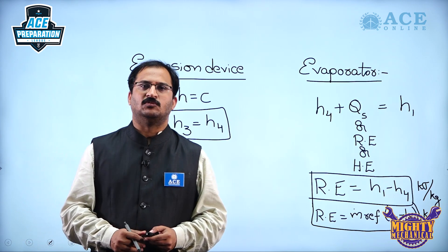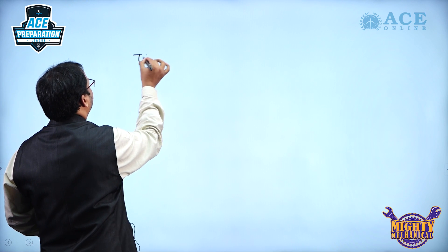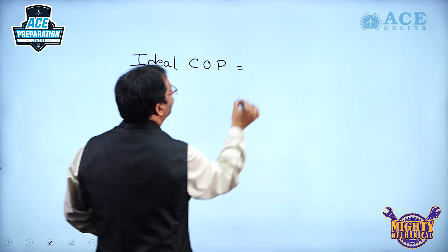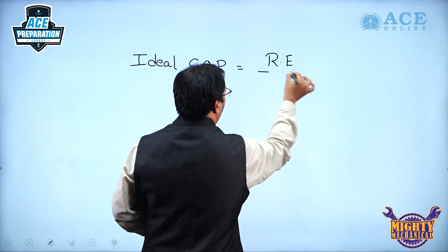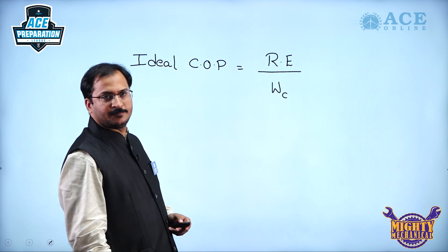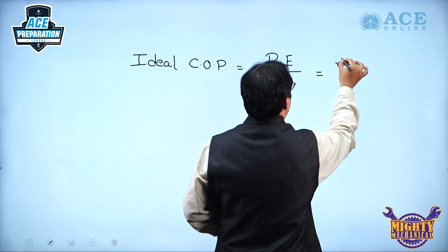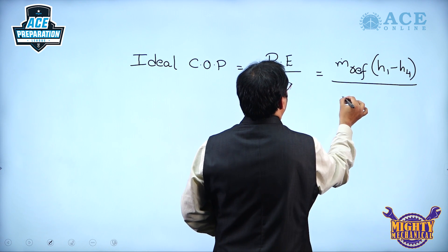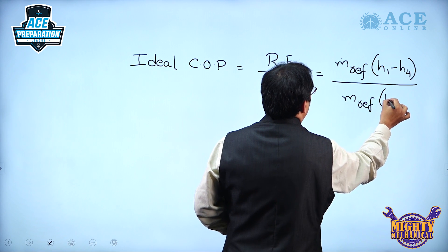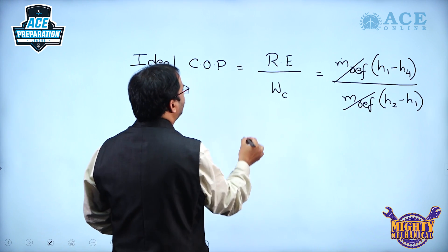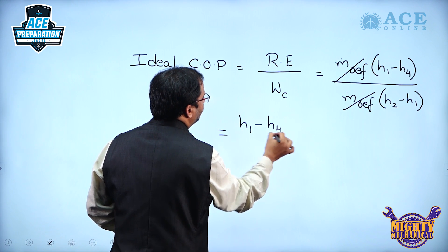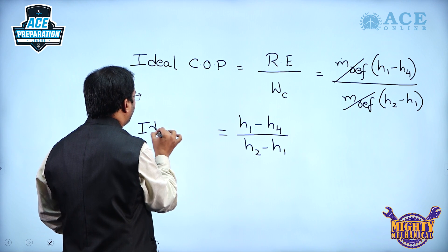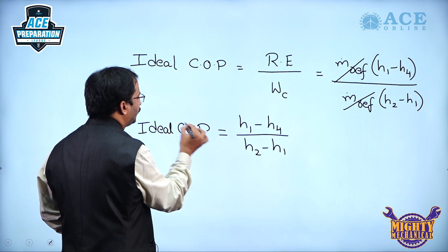Now, the ideal COP of the simple vapor compression refrigeration system is the refrigerating effect divided by the work input to the compressor: COP = (ṁ × (H1 − H4)) / (ṁ × (H2 − H1)). The mass flow rates cancel, giving the ideal COP as (H1 − H4) / (H2 − H1).